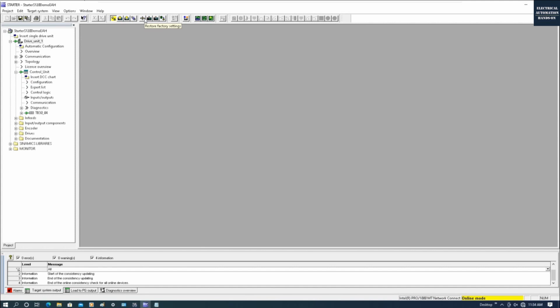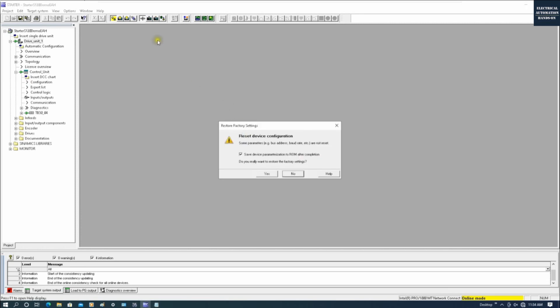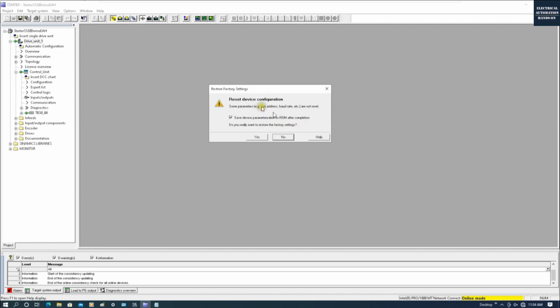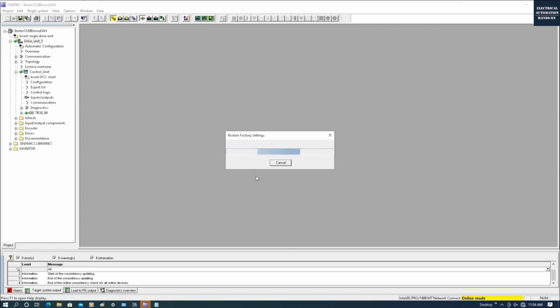So as we know, in some cases maybe this CU was tested in the factory. It might have settings inside. So I highly recommend you click this Reset to Factory. Click and reset device configuration. We can still save the IP address, baud rate, and some communication settings. Don't worry, they will not be reset. Okay, after we reset, we basically reset the ROM also, so we can click yes with this box checked. Okay, we restore factory settings.